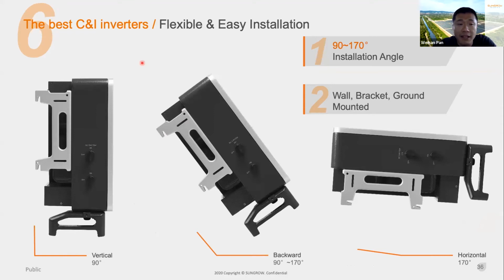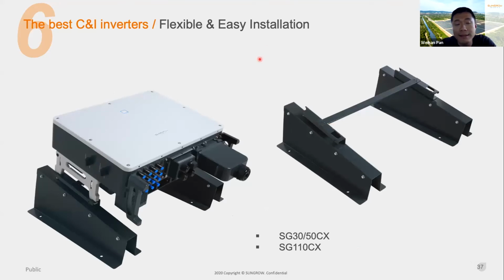And here is the flexibility and easy installation, because most inverters only support vertical installation. However, for some C&I projects, especially on rooftops, the area for the inverter is limited. So we also support up to 170-degree installation, which means from wall-mounted vertical installation to ground-mounted horizontal installation. And if the project needs to install the inverter horizontally, you might need to purchase this extra accessory, because even if the inverter is installed horizontally, you still need room for cooling circulation.